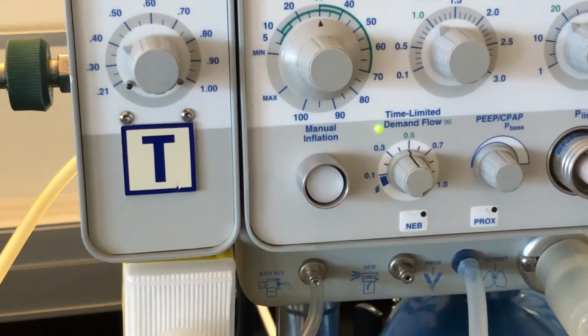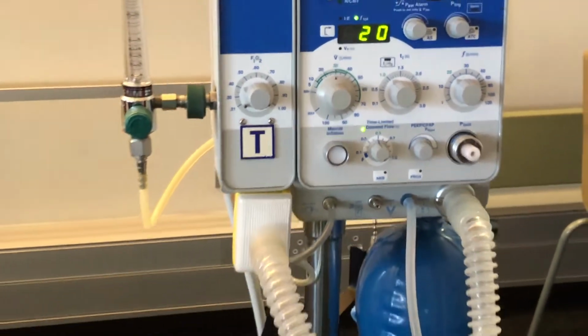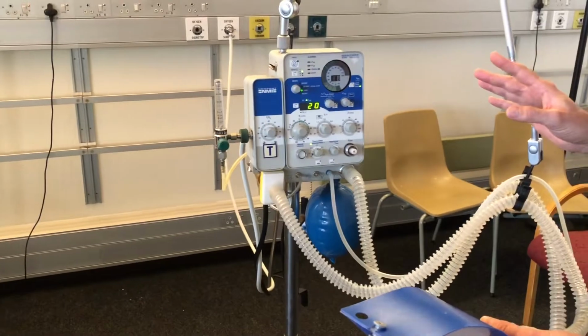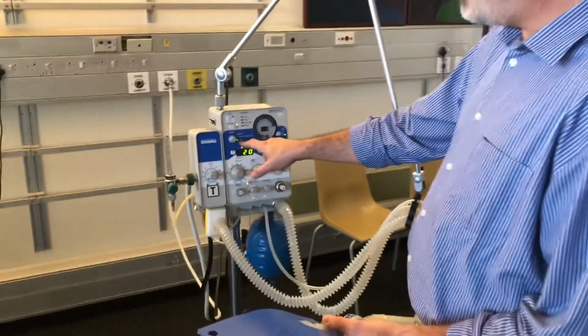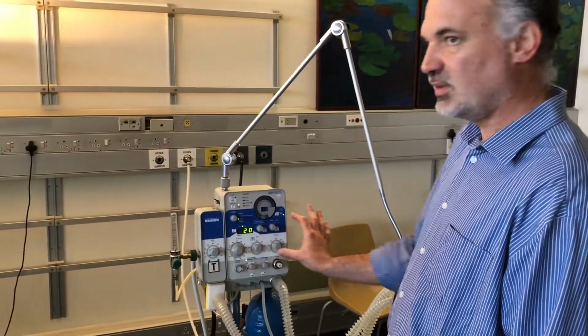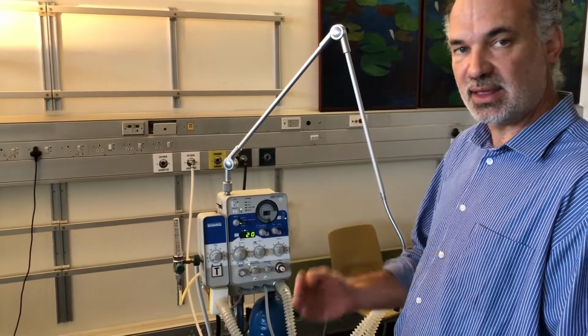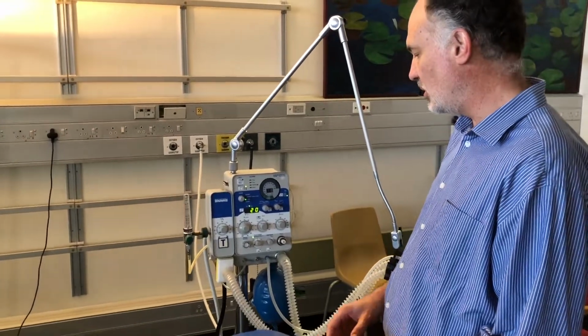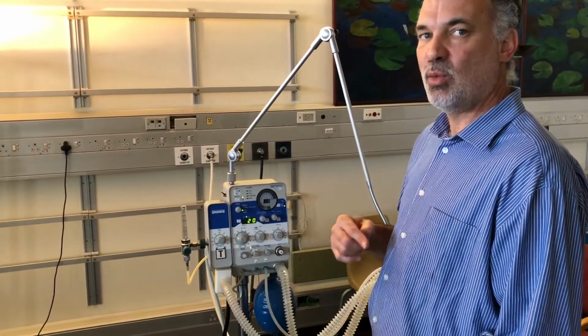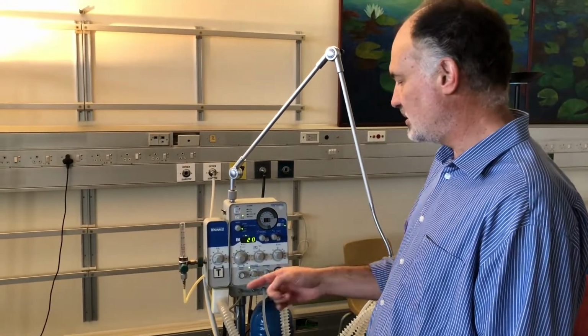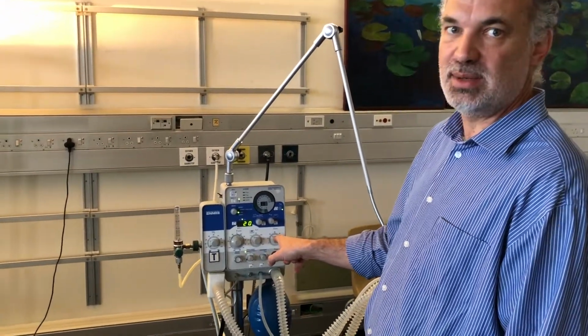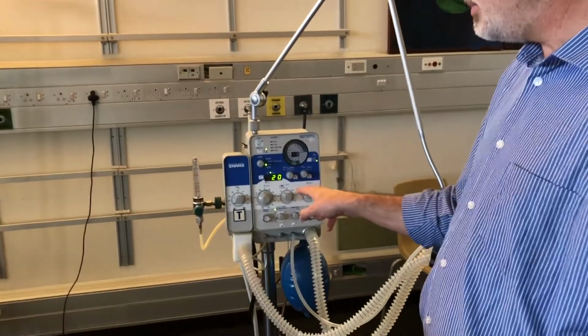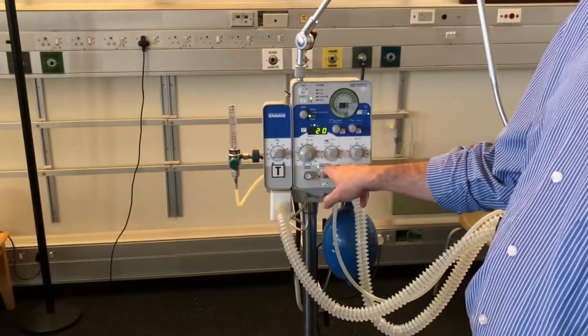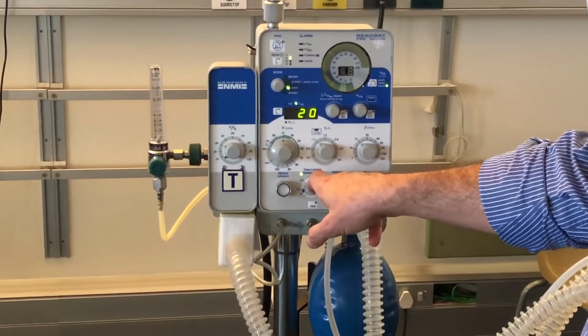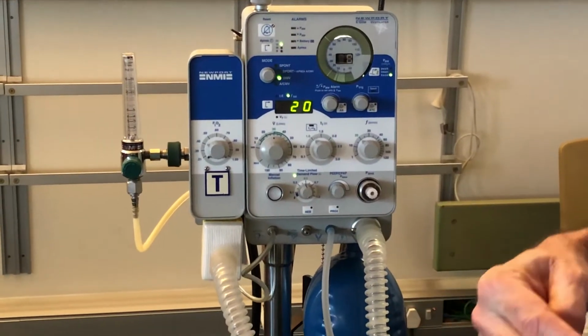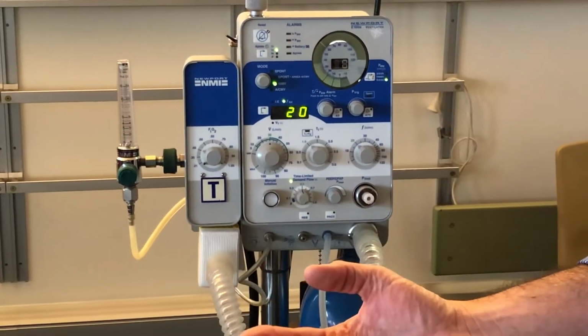So I said to you that this ventilator doesn't have pressure support. So the SIMV breaths are all delivered in terms of the settings that we've got there, just like the assist breaths in assist control. But if the patient now wants to take additional breaths, so they want to breathe more than 20 breaths a minute, then the breaths will be supported by the time-limited demand flow. In most modern ventilators, they'd be supported with pressure support.